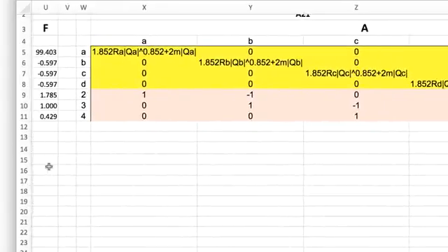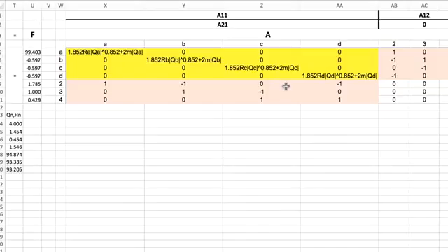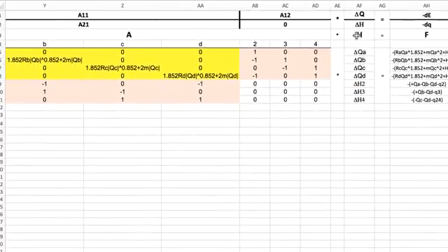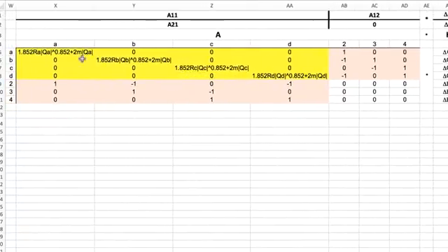Now, to set that up into a matrix solution that EPANET uses, as documented in the user's guide, is A times H is equal to F. I've provided some references down in the area below the video where there are other descriptions of how this matrix equation lines up, but we can break that down into A11, A12, A21, and 0.